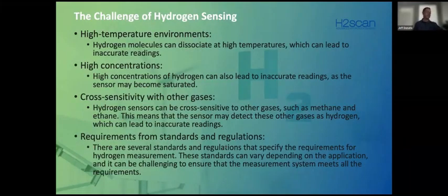So when it comes to hydrogen sensing, there are some challenges when it comes to actually creating a hydrogen sensor. Temperature plays a big part in the accuracy of the sensor. Certain sensors operate better in certain temperature environments, so you have to make sure you operate per the specification of the sensor itself.